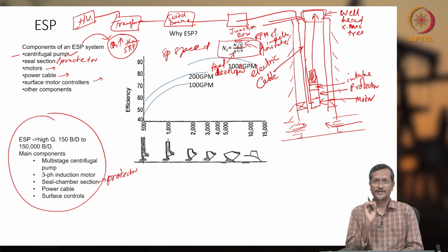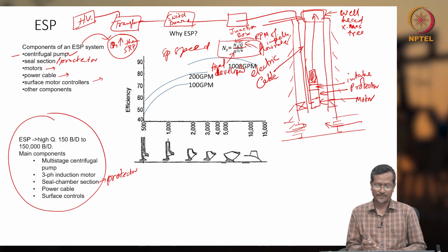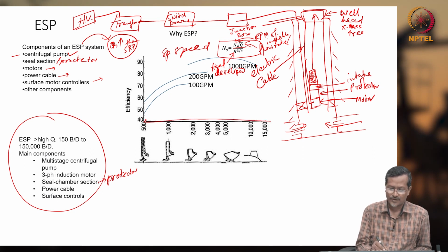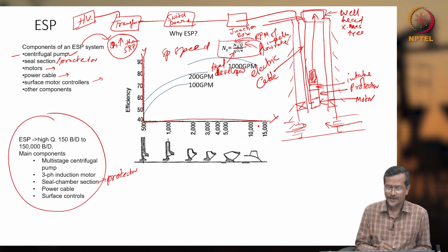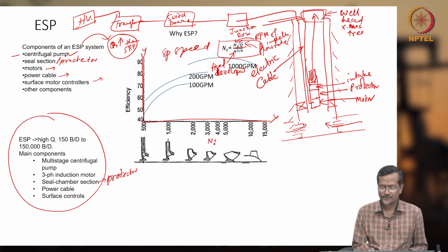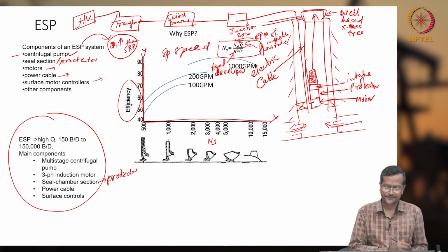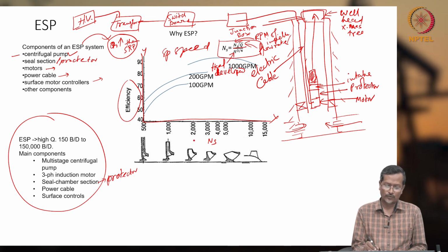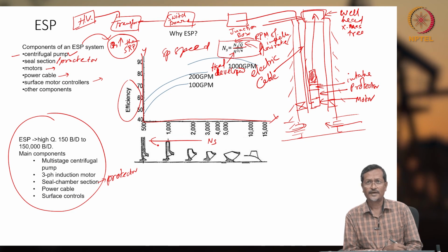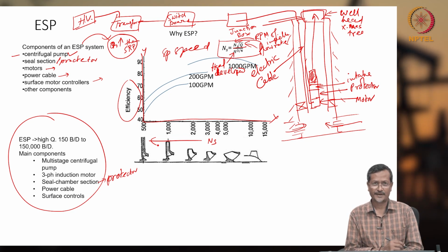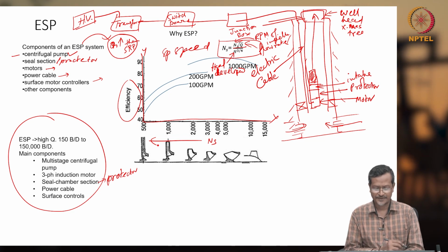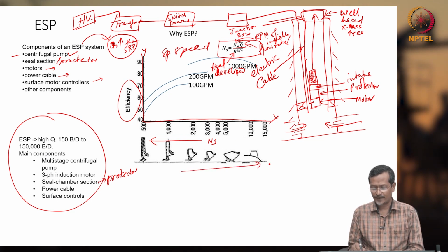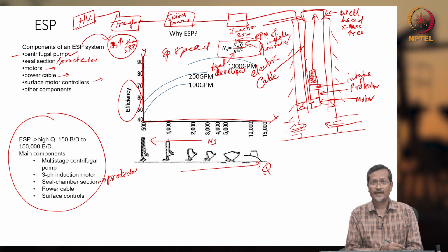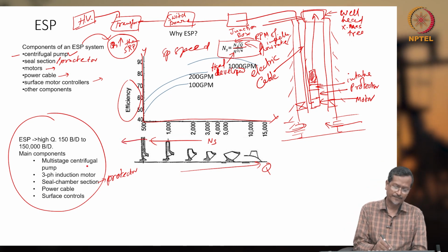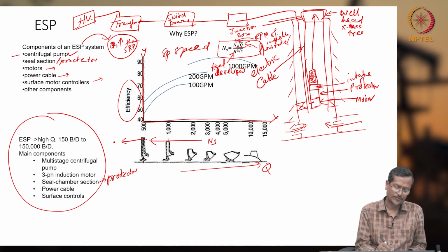Whenever you are saying specific speed and you want to represent it in terms of a curve, this is the x axis, this is the y axis. In the x axis you put ns values, and this is the efficiency value. If you go to lower specific speed, you are going to a radial type impeller. I will explain the radial type impeller later. I think in the previous lecture also I explained, again I will explain there. And if you are going for higher flow rate, Q higher, you are going towards an axial type system, and if you go further below in specific speed, then you can go for a positive displacement type pump.